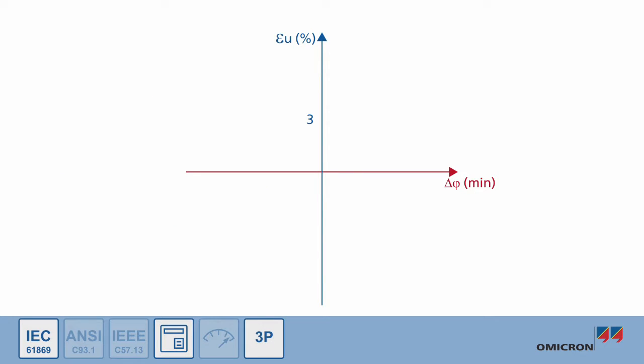3P is an example of an IEC protection class. Within the operating range, the error of a 3P voltage transformer must not exceed 3% in amplitude and 120 minutes in phase.